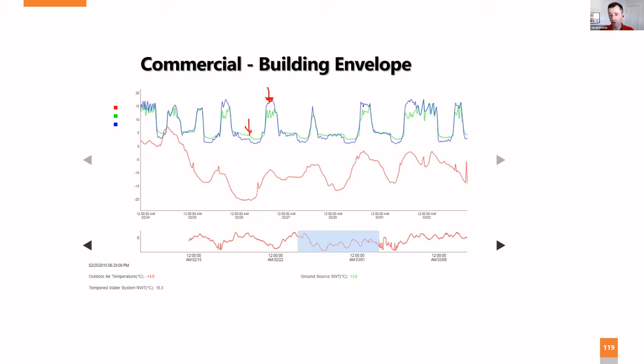Now there's a restaurant in there. So this building is most likely heating, cooling down to -15 or -20. And that doesn't mean every heat pump in the building's heating. The ones on the north are probably heating, but every internal and south zone is cooling. And so we saw that the entire week. At night, we're heating. During the day, when the people show up, all those internal gains and the sun hits that wall, we're rejecting heat to the ground loop. And so that's actually great news, and it's a lesson learned for envelopes for commercial buildings, especially because of those internal gains. There's no reason to have a great envelope.